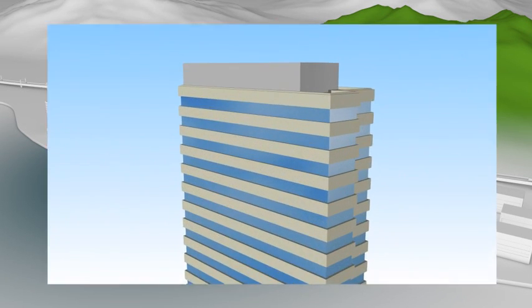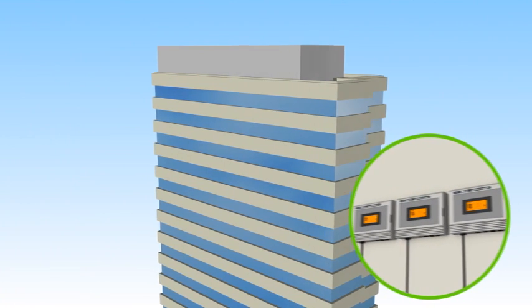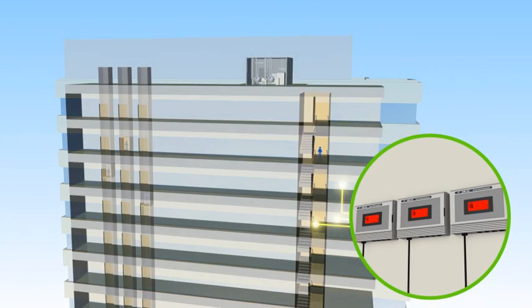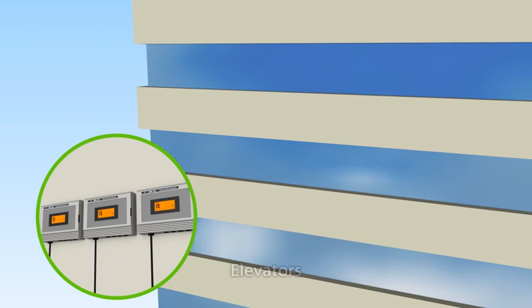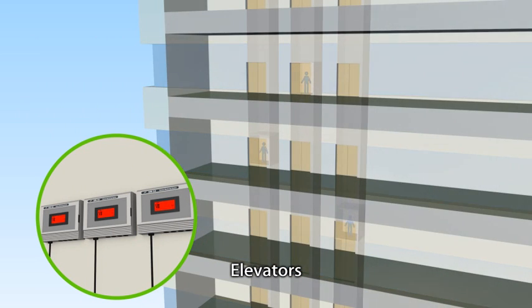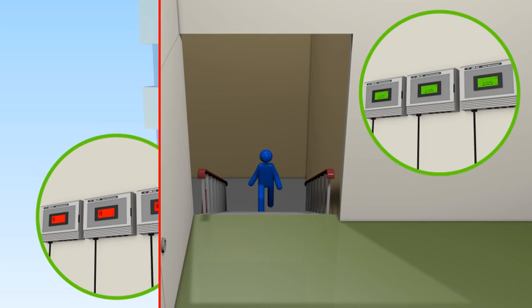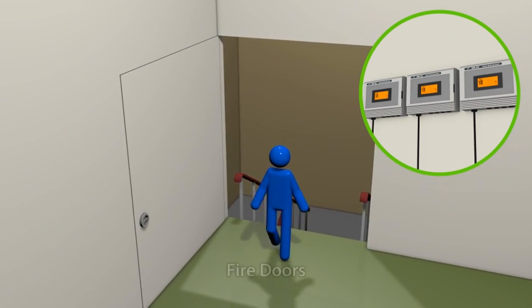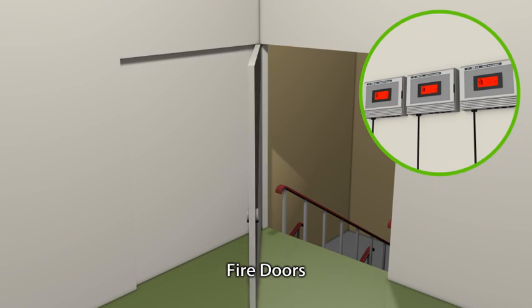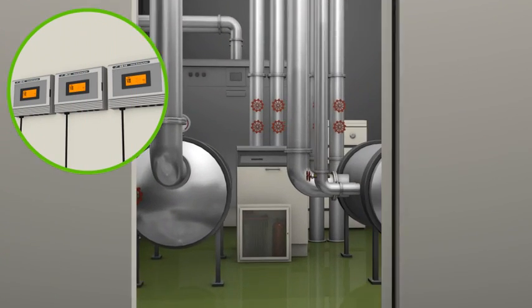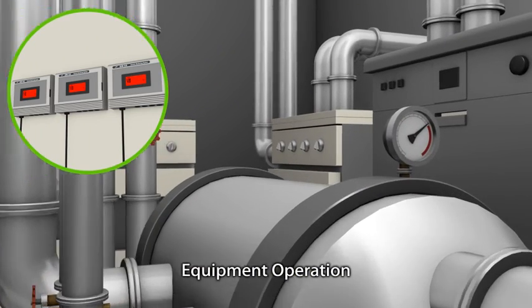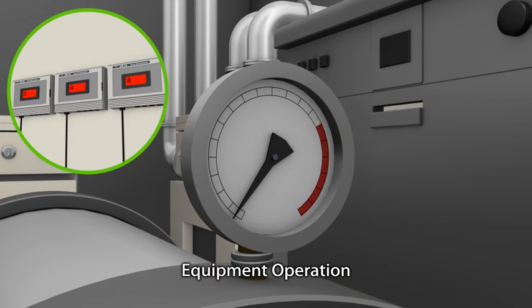Skyscrapers and tall buildings require safety measures against earthquakes as well. Earthquake monitoring systems can activate controls to automatically stop elevators on the nearest floors. They can activate disaster prevention measures such as fire doors. They can also initiate safe stopping of fragile and damage-prone equipment, like boilers or air-conditioning systems.